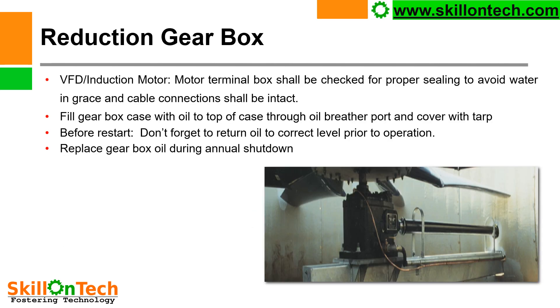Reduction gearbox — here you can see the reduction gearbox, which is coupled with a motor through a carbon composite drive shaft and coupling. Generally, variable frequency drive induction motors are installed. The motor terminal boxes shall be checked for proper sealing to avoid water ingress into the terminal box, and cable connections shall be intact. The gearbox shall also be inspected for oil level. If there is a lack of oil, fill the gearbox case with oil through the oil breather port. Before restarting the fan, do not forget to return the oil to the correct level prior to operation. Gearbox oil shall be replaced annually during the annual shutdown.